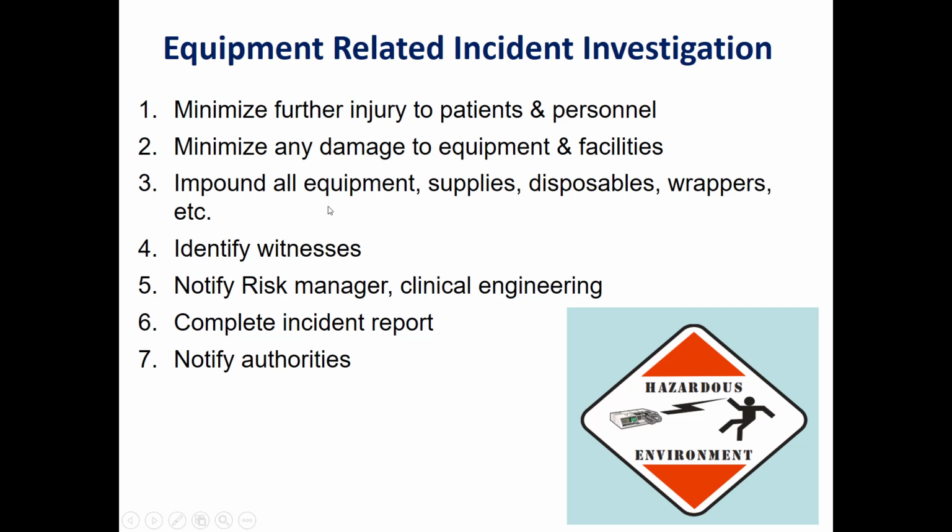We should impound all equipment, supplies, disposable wrappers, and everything. We should identify the witnesses. After that, we will make a notification to the risk manager and the clinical engineering about the situation. We complete the incident report, and finally we should notify the authorities.